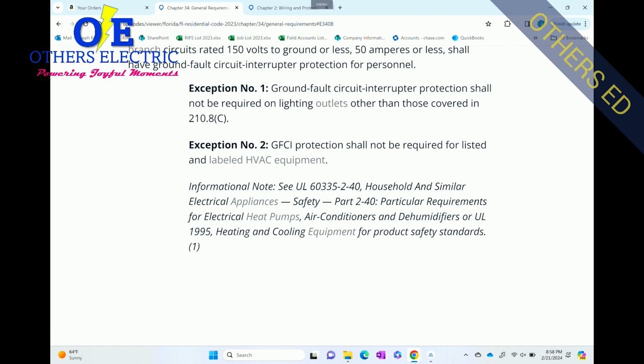So, guys, there you have it. Yes, all outdoor outlets have to be GFCI protected if they're 50 amps or less inside a residence, except for HVAC equipment. That will change because they are changing the UL listing requirements for HVAC equipment, but I think it's going to change on January 1st, 2026 or something like that. So until further notice, you do not have to put outdoor HVAC equipment on a GFI breaker.